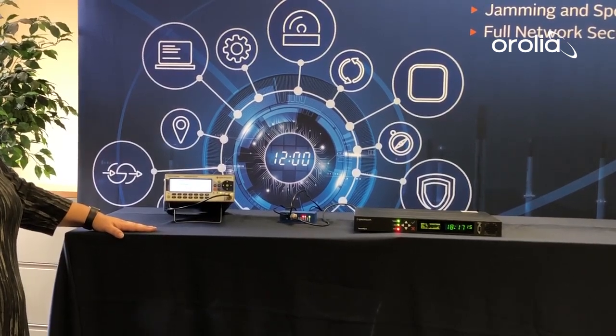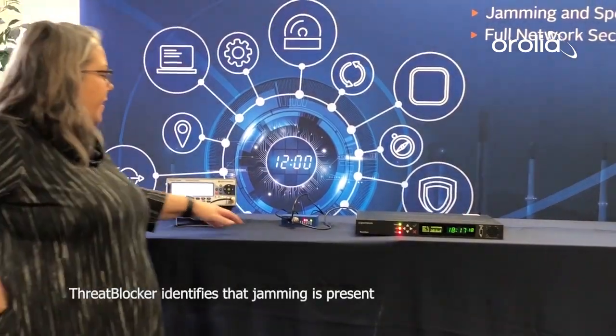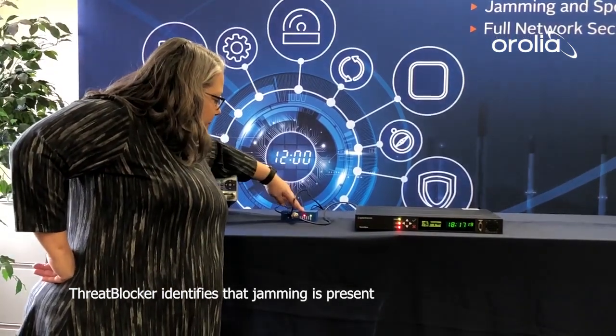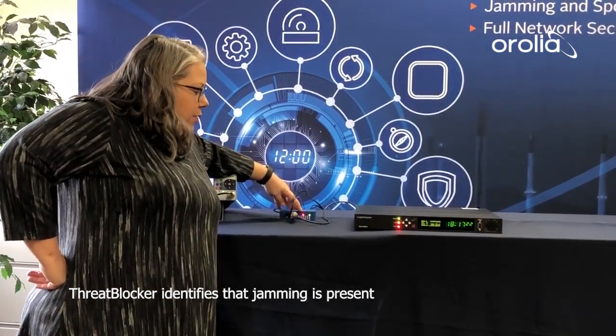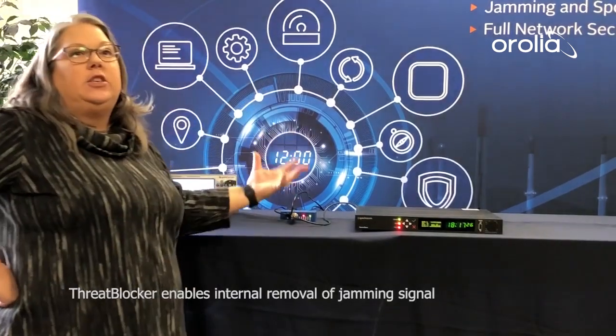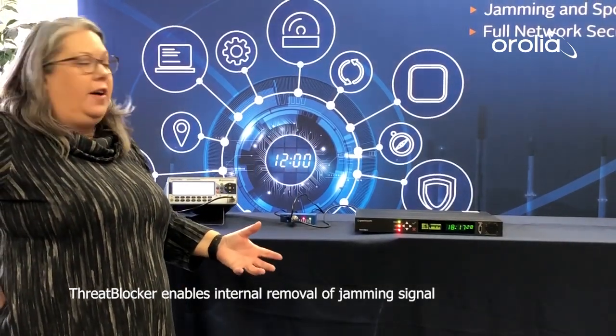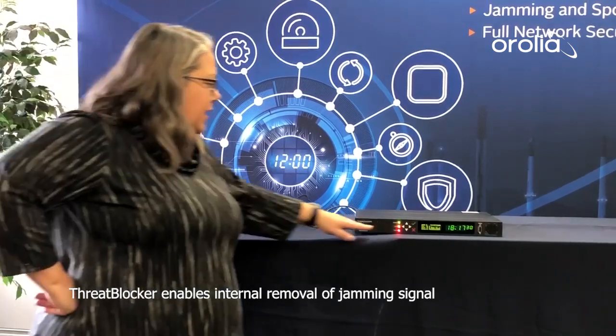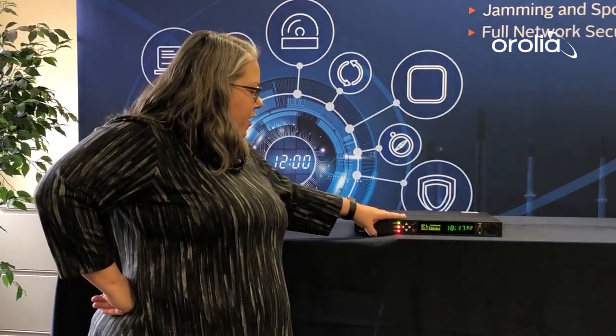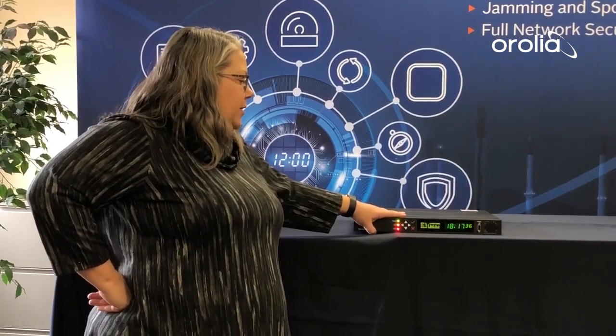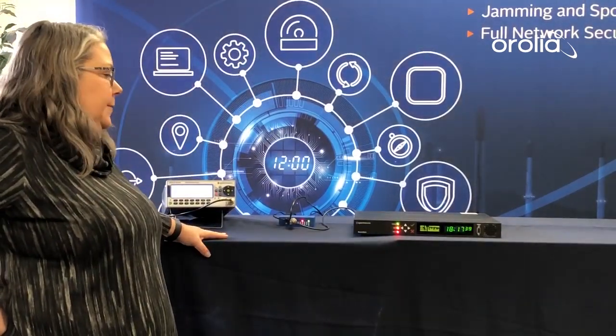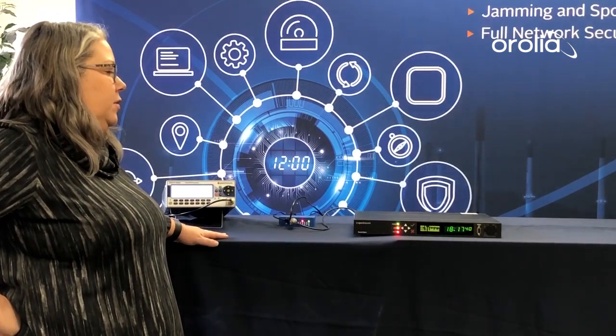So now the jamming signal is just starting. ThreatBlocker identifies that there's jamming present. So it's locked on here. And then what ThreatBlocker does is it enables its internal removal of the jamming signal. So we should see here this reacquire our satellites and go back into sync and operate as normal. We just have to give SecureSync a minute to clear its alarms.